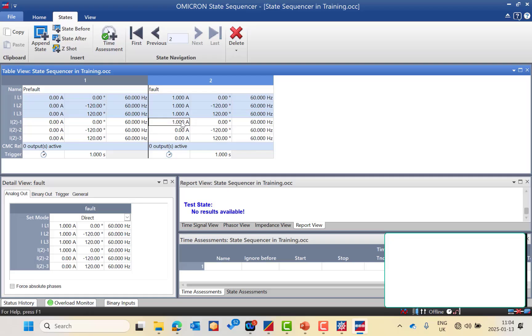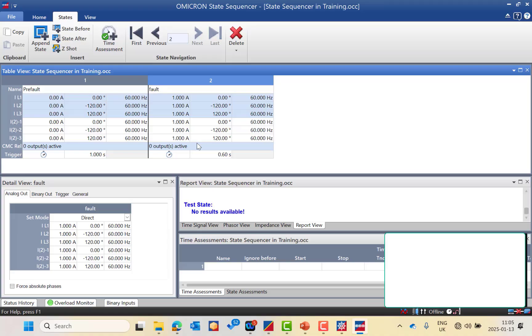I can do the same for the other values. I can also set the timeout — for example, if I am expecting 500 milliseconds, I can make it 600 milliseconds (0.6 seconds). Or you can configure the state to switch off on trigger by any binary input.